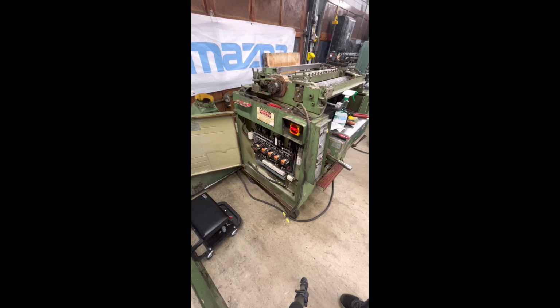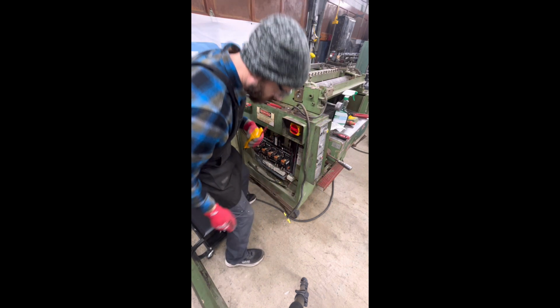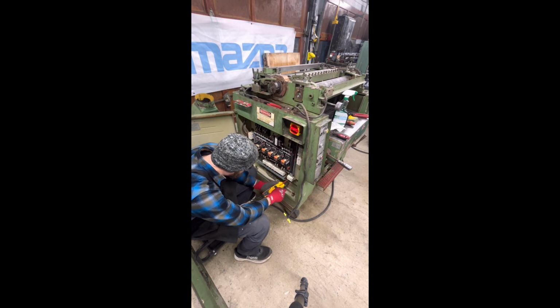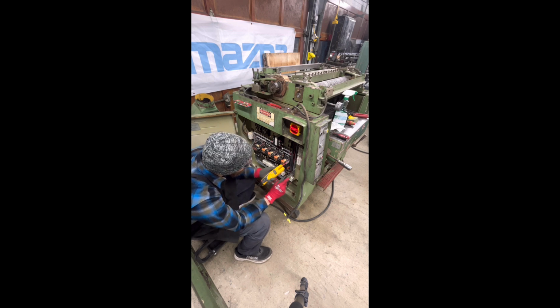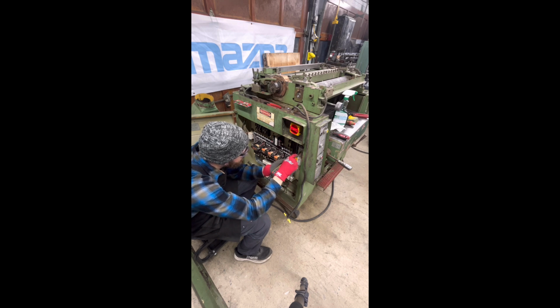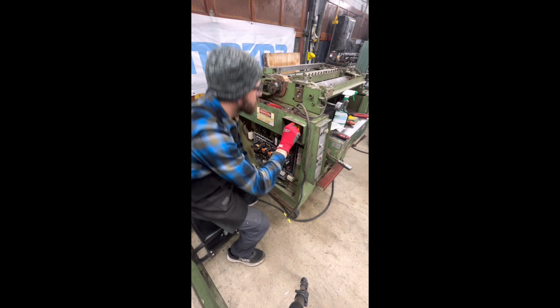Fire up the rotary phase converter here and double check voltages and everything again. Need to be very careful when working inside of an electrical cabinet. This is fairly high voltage here. You'll see me stand up eventually after checking the voltages here when I turn the disconnect on. I always want to get my face away from an open electrical cabinet when energizing it, just because of arc flash and something could blow up.